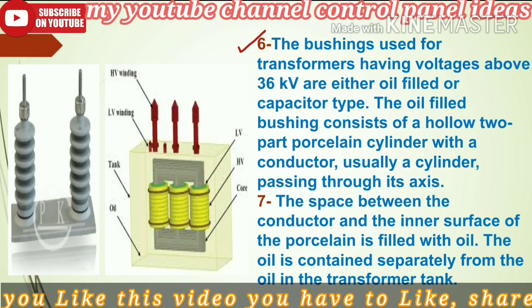Point 6. The bushings used for transformers having voltage above 36 kV are either oil filled or capacitor type. The oil filled bushing consists of a hollow two-part porcelain cylinder with a conductor, usually a cylinder, passing throughout its axis. Point 7. The space between the conductor and the inner surface of the porcelain is filled with oil.